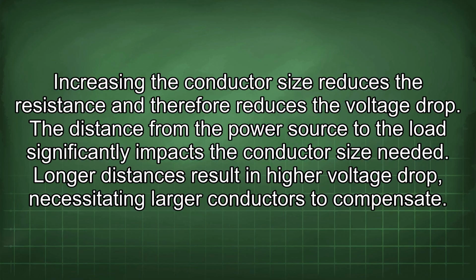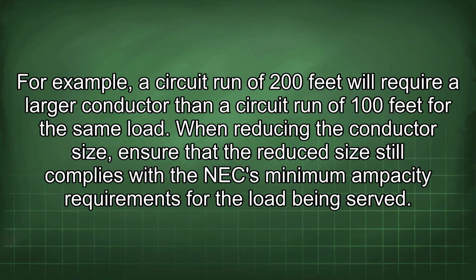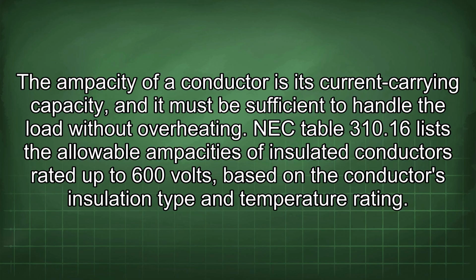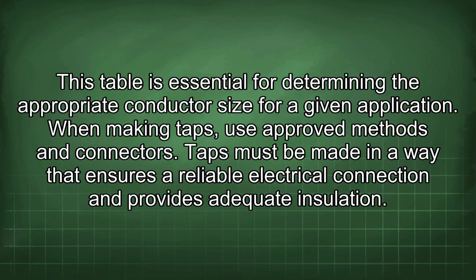The distance from the power source to the load significantly impacts the conductor size needed. Longer distances result in higher voltage drop, necessitating larger conductors to compensate. For example, a circuit run of 200 feet will require a larger conductor than a circuit run of 100 feet for the same load. When reducing the conductor size, ensure that the reduced size still complies with the NEC minimum ampacity requirements for the load being served. The ampacity of a conductor is its current carrying capacity, and it must be sufficient to handle the load without overheating. NEC Table 310.16 lists the allowable ampacities of insulated conductors rated up to 600 volts, based on the conductor's insulation type and temperature rating.